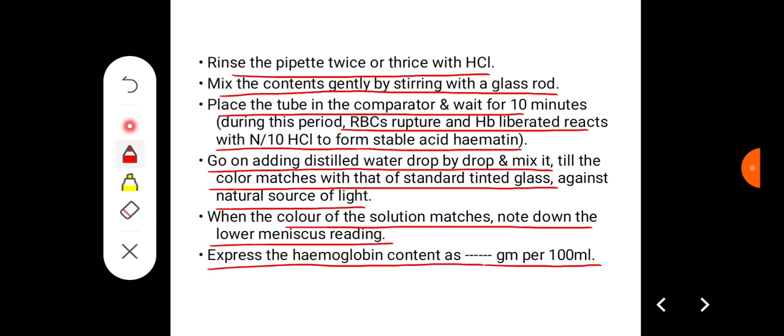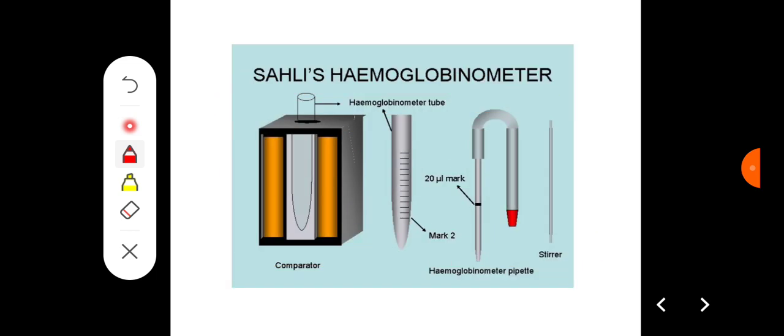These are the diagrams showing Sahli's hemoglobinometer. This is Sahli color comparator with a hemoglobin tube or Sahli tube. This is a Sahli tube with the markings of 2 to 100 in percentage. This is hemoglobin pipette. You have to take the N/10 HCl up to the mark 2, then you have to suck the blood up to the mark of 20 microliter mark.